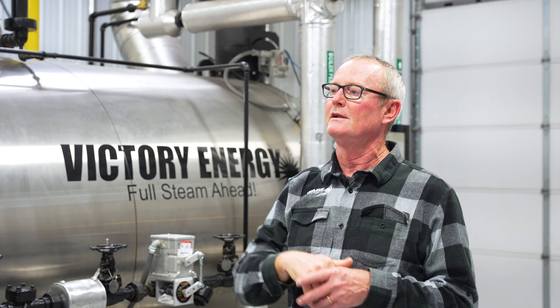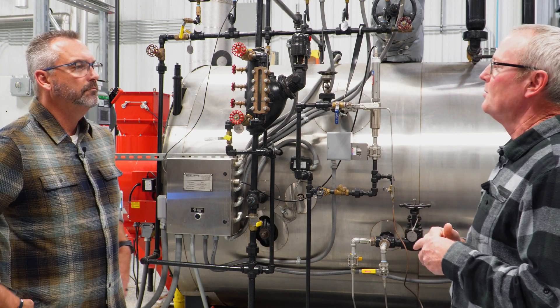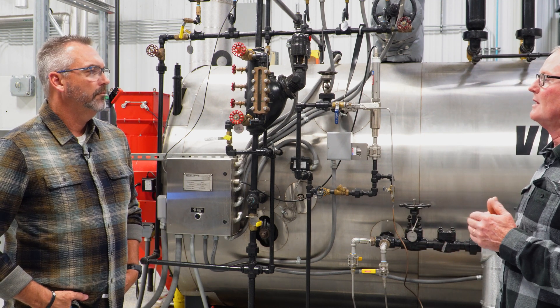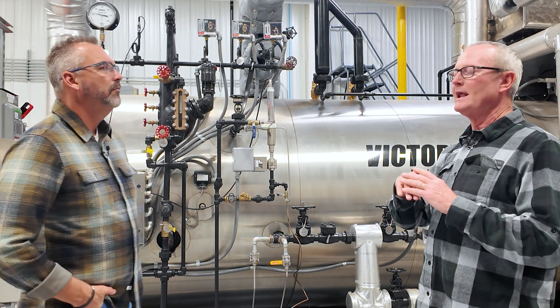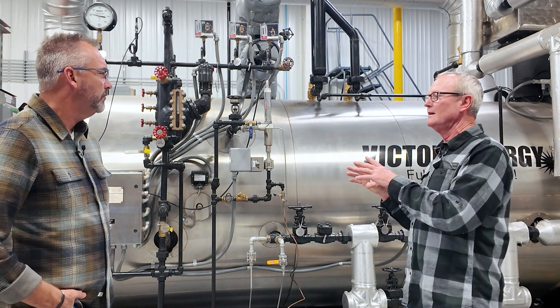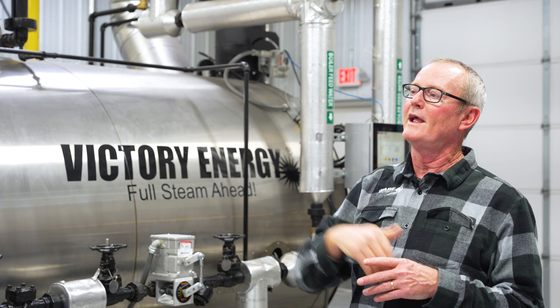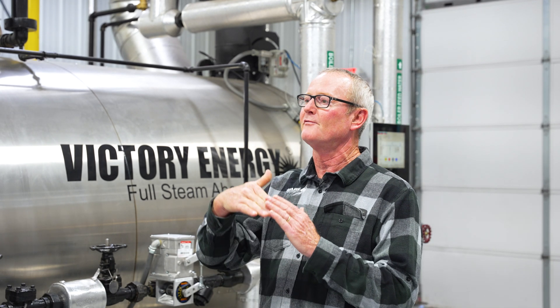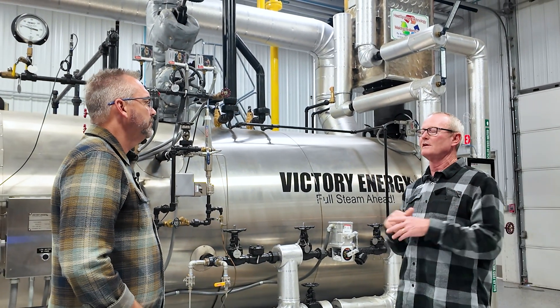So we can run these boilers at rate. Most of the time those are slow-opening valves. If you've got a kiln, those types of things are typically not slow open — they'll have an actuator on them and they'll pump it wide open. And if it's wide open and the boiler can't produce steam as fast as they're dumping it in there, we'll have them slow that actuator down. It has almost no effect on the process they're doing in the kiln, but it makes a huge difference in the boiler being able to keep up with the load. Instead of a five-second opening, you make it a 60-second opening where it takes a minute to fully open. Then the boiler can keep up with it and nobody ever knows it — the plant doesn't know it, the boiler doesn't know it. It just slows everything down.